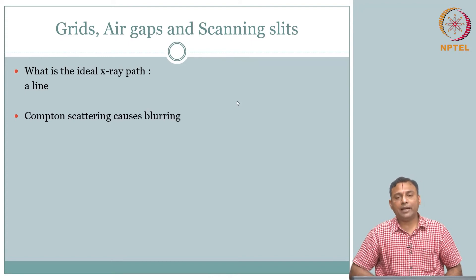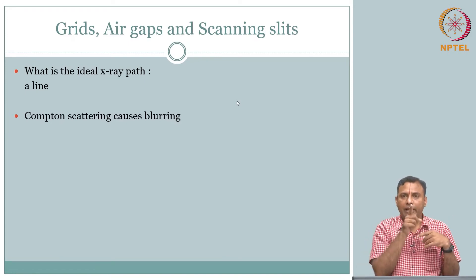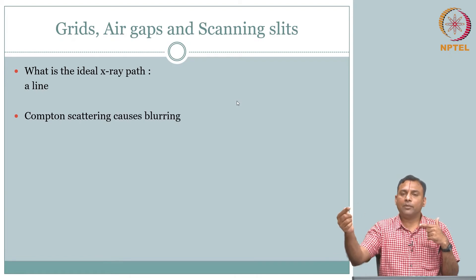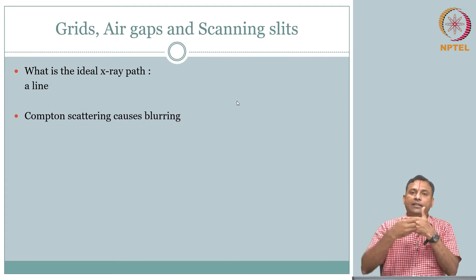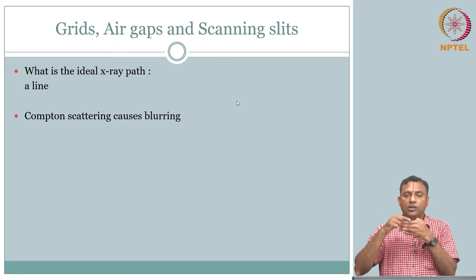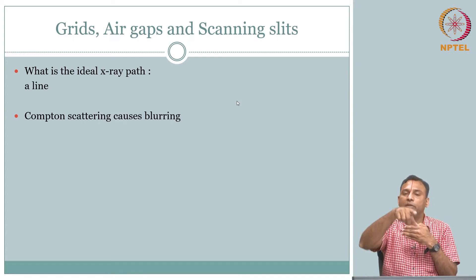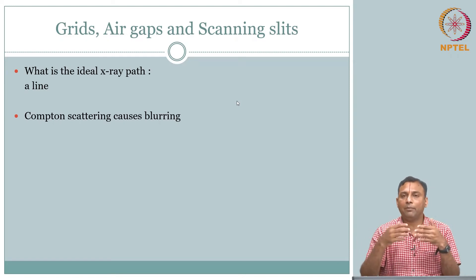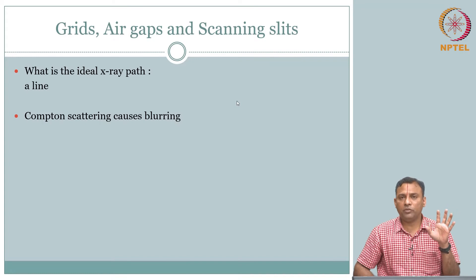Compton scattering essentially causes blurring. I am looking at the straight-line path, but a Compton-scattered photon comes and hits the detector. My model can only assume it came from the straight line, so whatever came from scattering gets incorrectly attributed — blurring your resolving capability. This is undesirable and we need to reduce it. Maybe we can create a kind of filter — a gating mechanism — before it hits the detector: I will only allow photons coming along the straight line and block those coming from the sides.